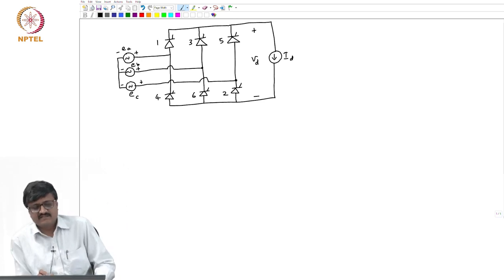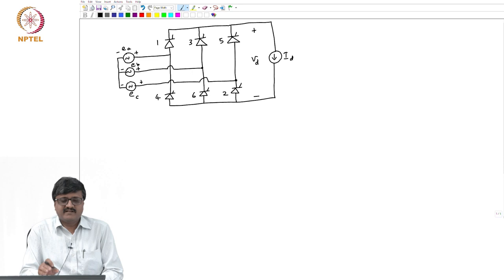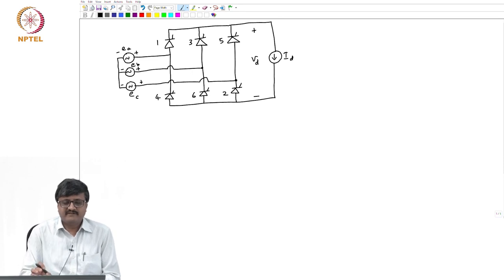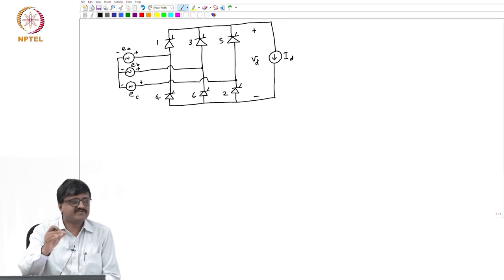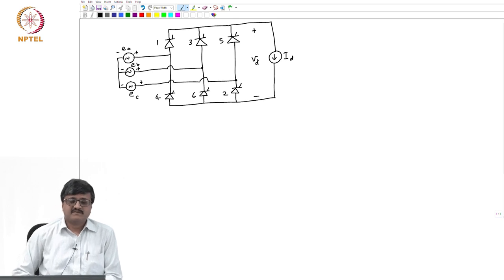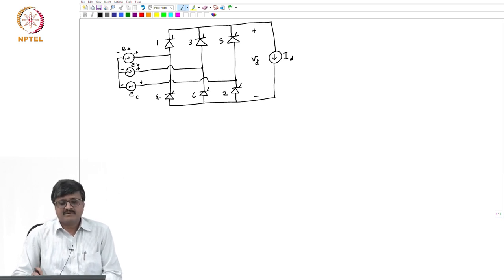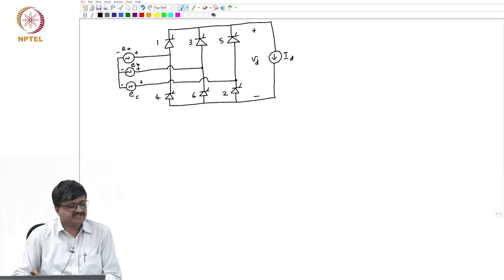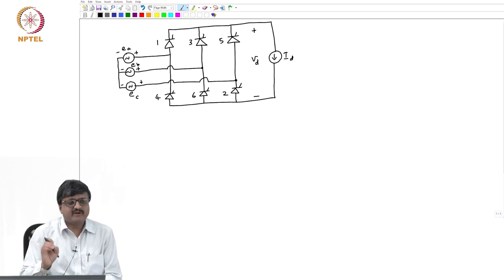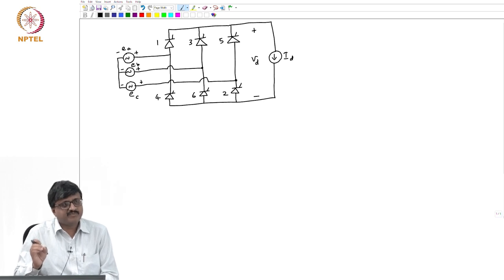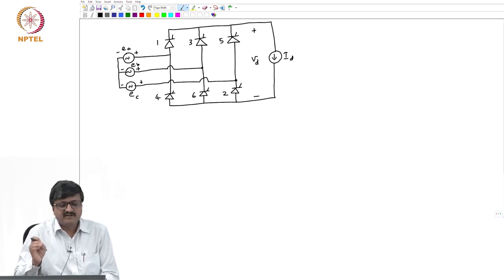We saw in the last class that I can divide the converter into two basic commutation groups: upper commutation group and a lower commutation group. Valves 1, 3, 5 form the upper commutation group; valves 4, 6, 2 form the lower commutation group. At any instant only one thyristor valve in any commutation group conducts — that is one among 1, 3, 5 and one among 4, 6, 2.